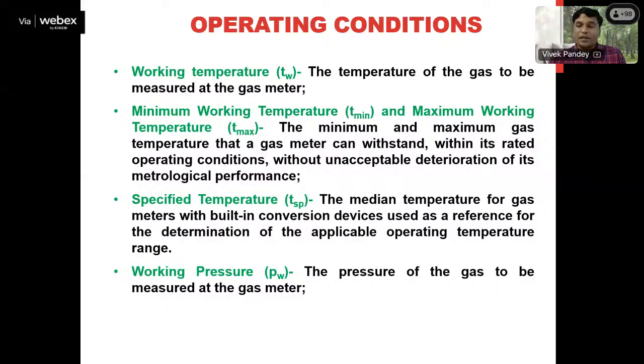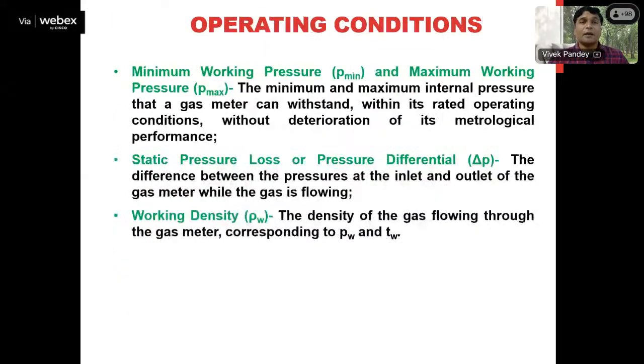Now there is a working pressure also specified, which should be measured when the gas meter is being operated, with the help of a calibrated manometer. That means the current pressure of the gas. Then there is a pressure range specified by the manufacturer, the minimum to maximum pressure range within which the accuracy of the gas meter will be intact. So that is also specified.